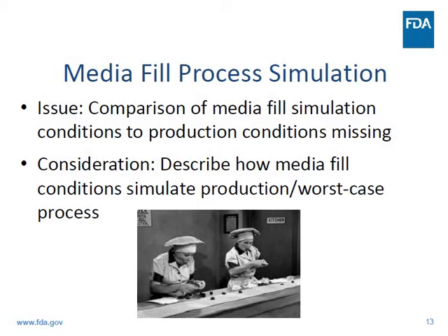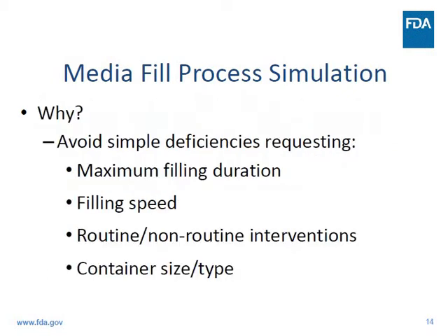And here the benefit is that by providing this information, you can avoid simple deficiencies requesting things like the maximum filling duration for your simulation or process, the filling speed used for production and the simulation, what interventions were used, and what container was used for the media fill simulation.